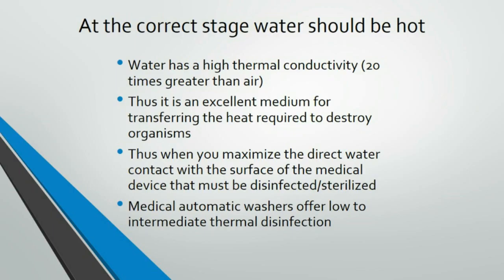So at the correct stage, as I said, we do want our water to be hot. And that's because water has a high thermal conductivity, 20 times greater than air. It is actually able to move temperature, bring it in and pass it off or release it to the next thing, which is what we want, right? We want it to contact instruments.